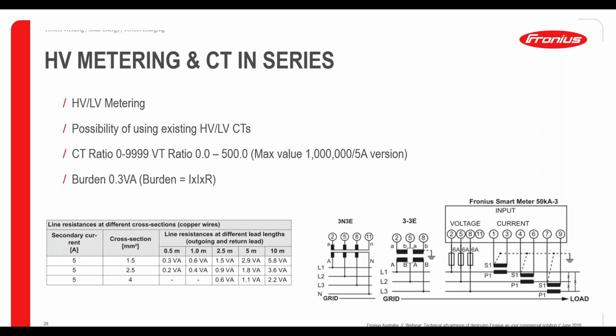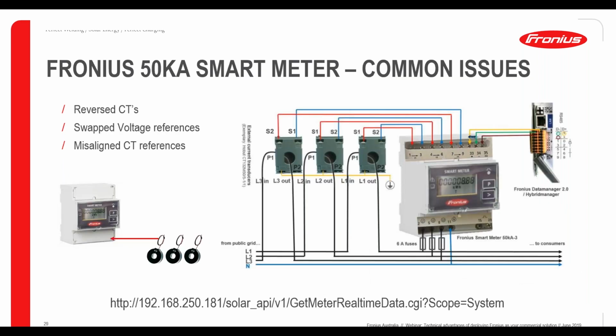This is a typical deployment with current measurement output, such as 5 amp CTs. So you could potentially use existing CTs outside, obviously subject to DNSP approvals and customer approvals and so forth. If we continue onward, a typical common issue we've seen with this meter is that the CTs are not installed in the right direction. Rule of thumb, what you need to be cautious of: all CTs come with measurement S1, S2, and P1, P2. P1 always measures the source, which is your grid, and if that's the case, then S1, as configured, will be the source on the secondary circuit.